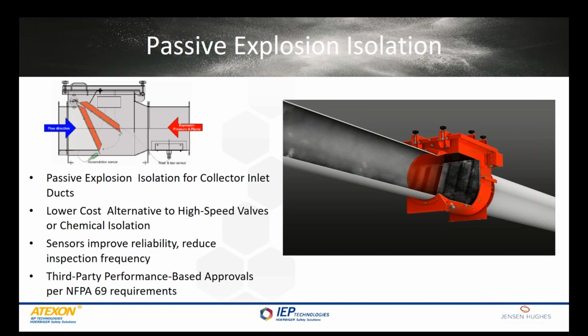One of the very important functions of these valves is that they have to be in a level or flat or horizontal type of orientation in order for the valve to work properly. So this is something to consider when designing, say, a dust collection system for a biomass facility. You want to take advantage of this style of isolation barrier. You want to make sure that when the duct routing is being designed, you take into consideration that there's a certain minimum distance upstream in which this valve has to be placed before you can start branching out and doing your other pickup points.